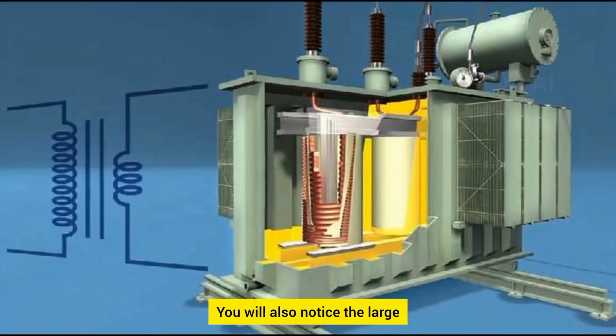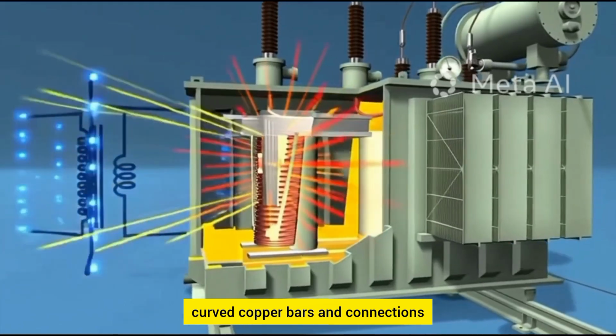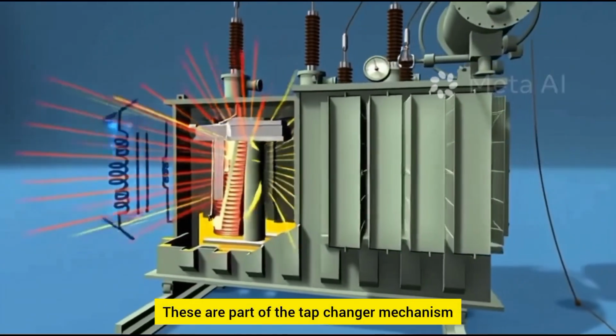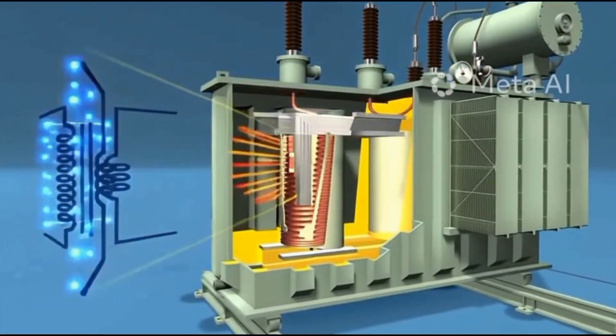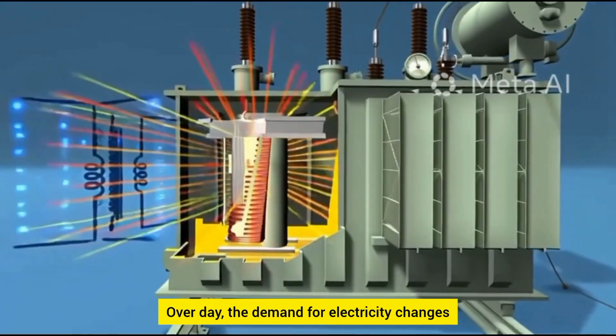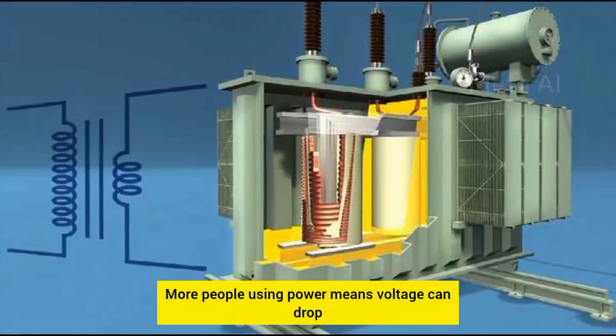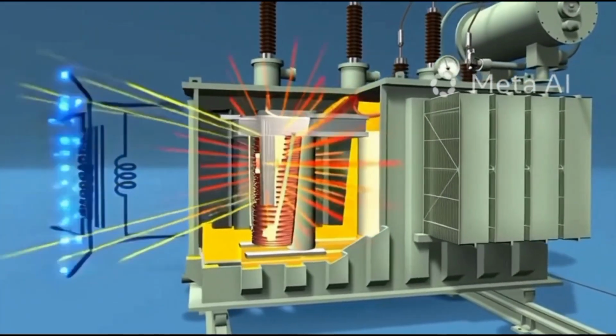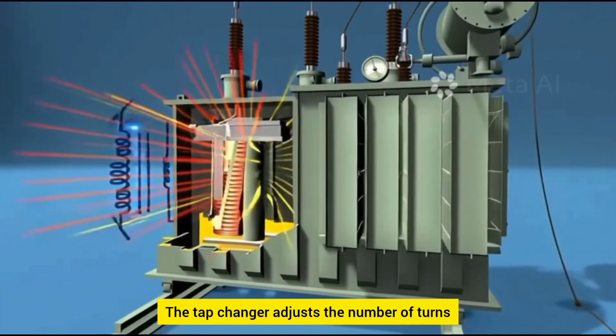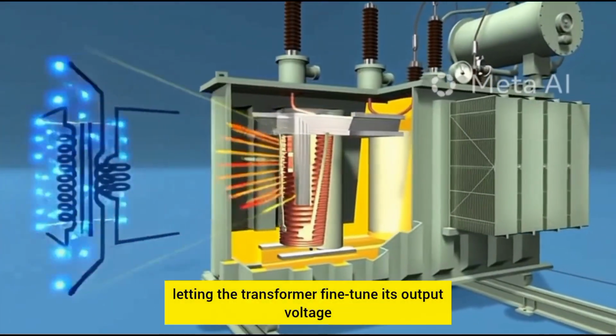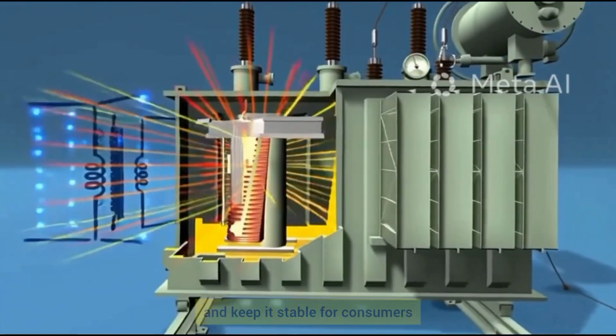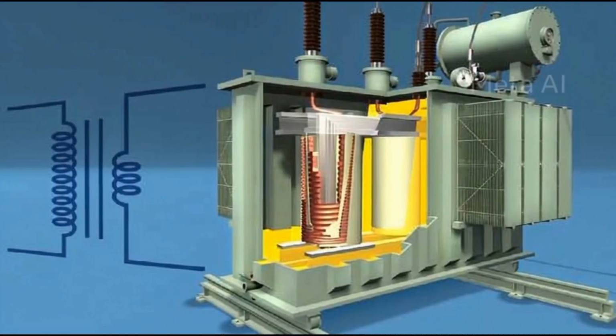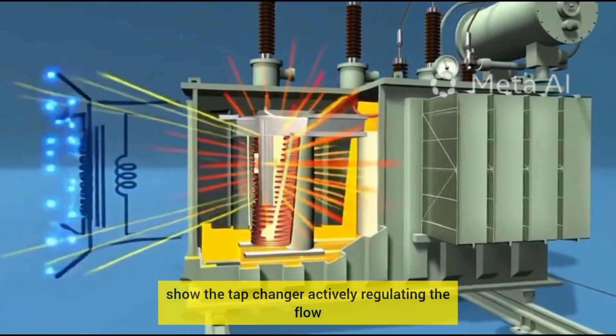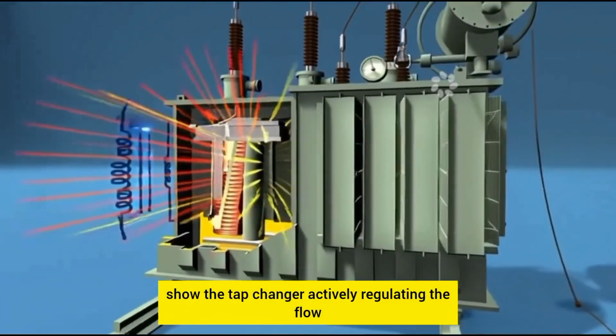You will also notice the large, curved copper bars and connections. These are part of the tap changer mechanism. Over the day, the demand for electricity changes. More people using power means voltage can drop. The tap changer adjusts the number of turns used in the winding, letting the transformer fine-tune its output voltage and keep it stable for consumers. The light pulses shifting through these bars show the tap changer actively regulating the flow.